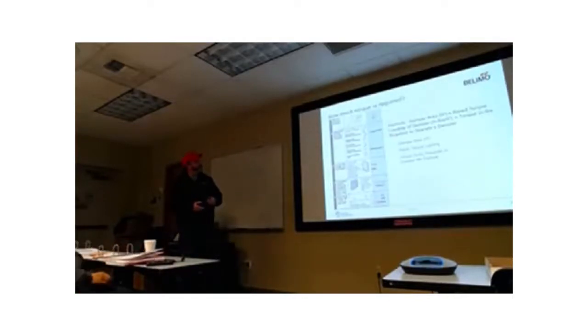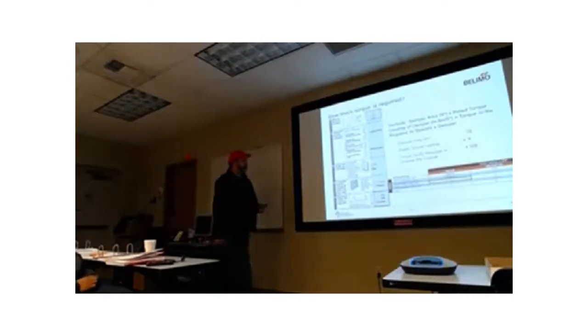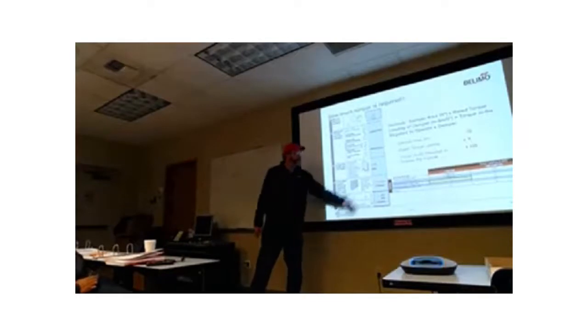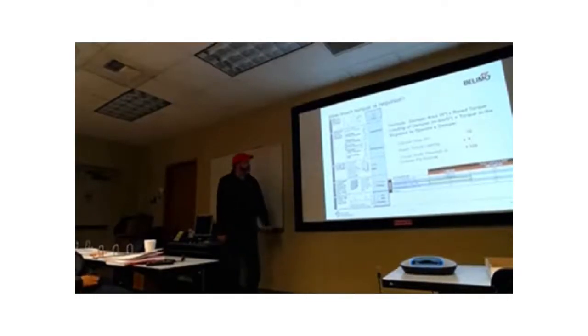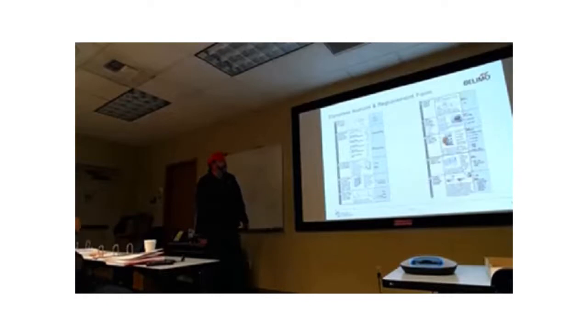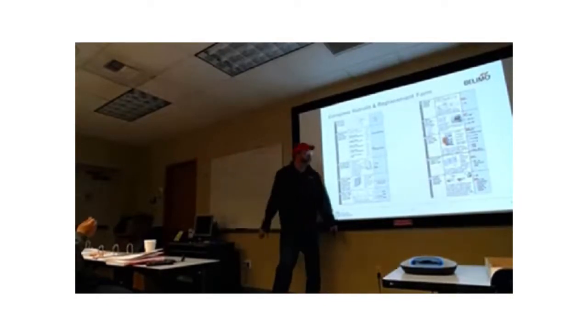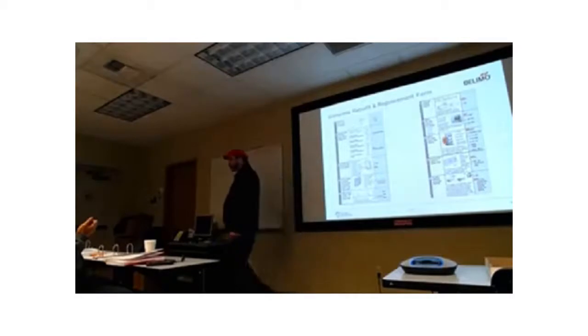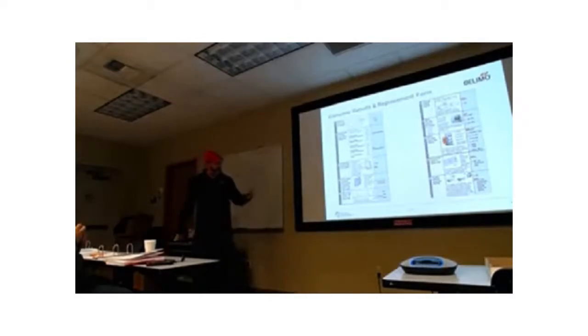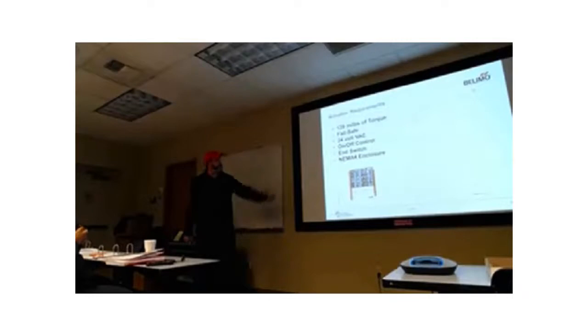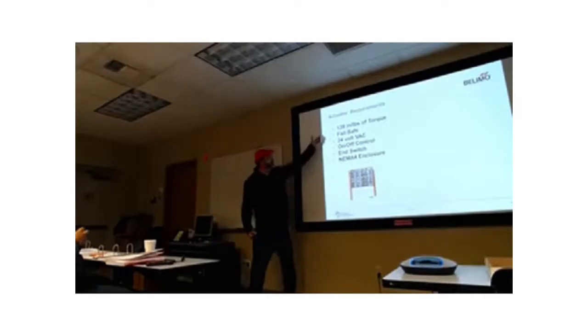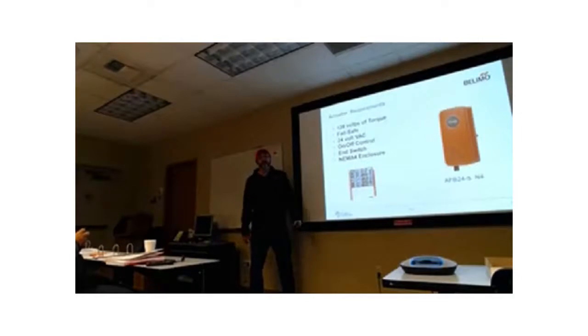All right, let's go back through it again and beat the dead horse. We got a 32 square foot damper with parallel blade, no seals. The actuator torque is 128, so we picked an AF, with a fail-safe 24 volt, 2-position actuator coupled directly to the shaft, and a NEMA 4 enclosure. Here's all the data we just talked about. Ta-da.